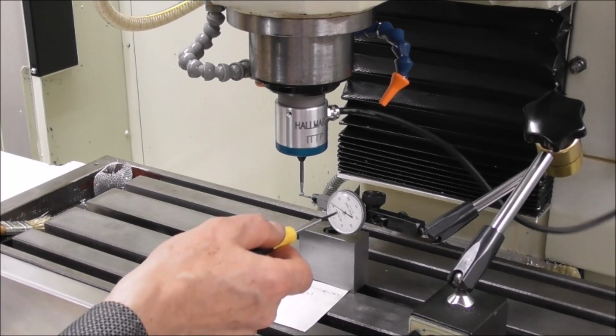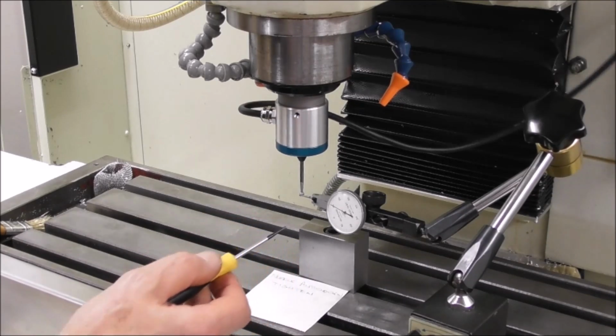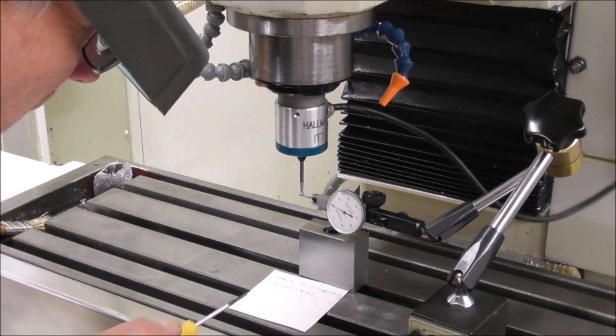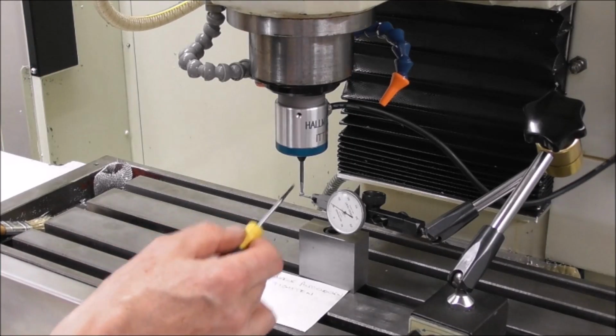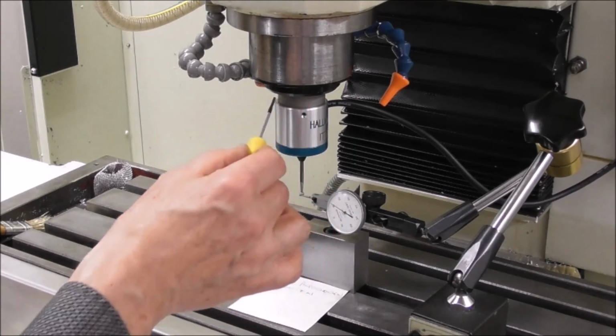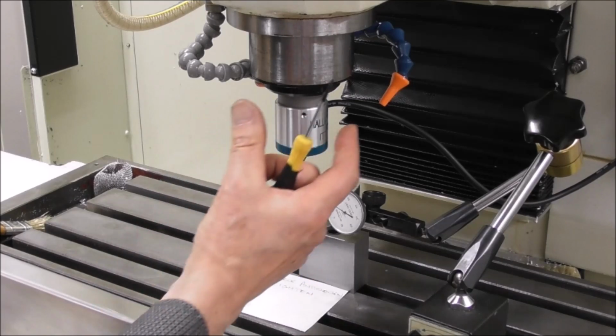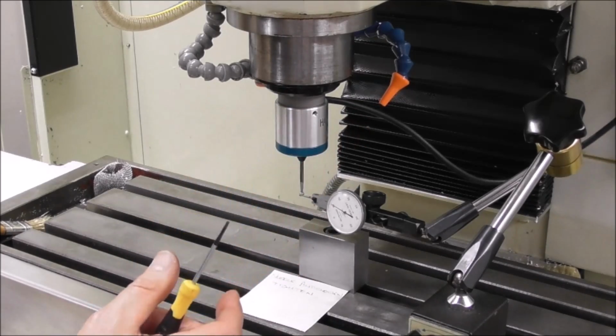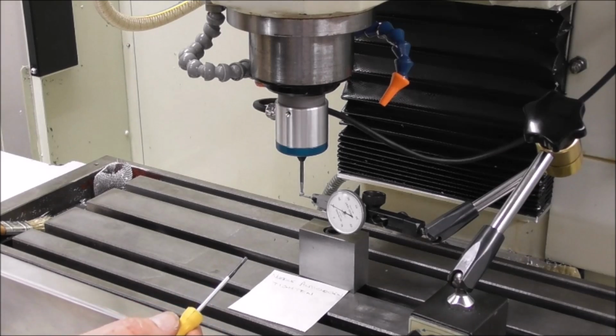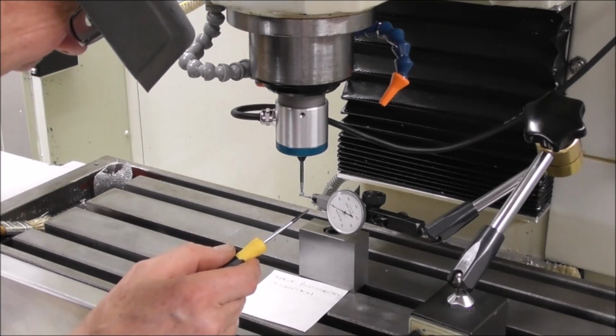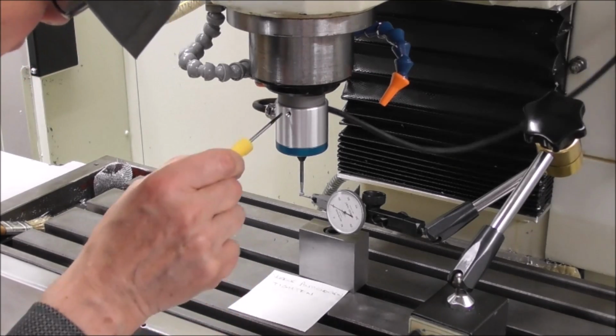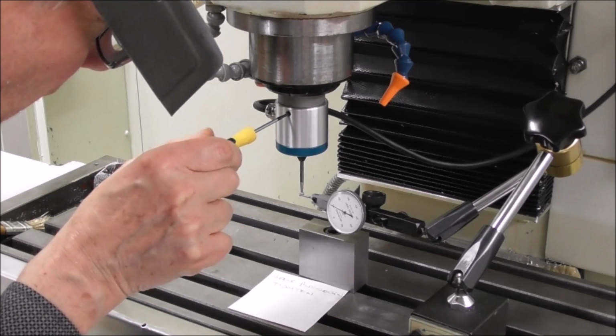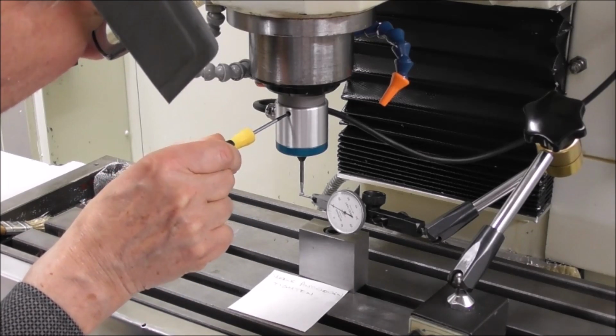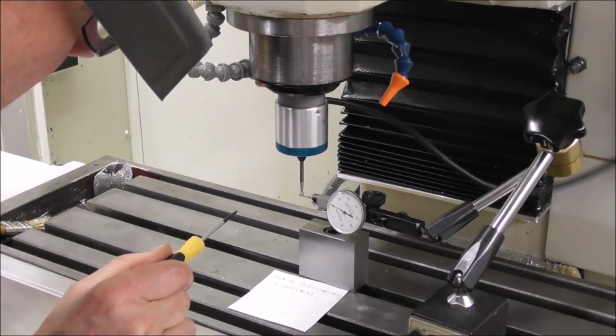Okay, now with about 3 adjustments we've got it within, what's that? Within about 100th. So what we would do now, we've passed the stage of backing off and tightening and shunting the probe into place. Now we want to snug up the screws. So go to its most anti-clockwise position, which is there, snug up the screw, leave it snugged up, just give it a slight little bit there.